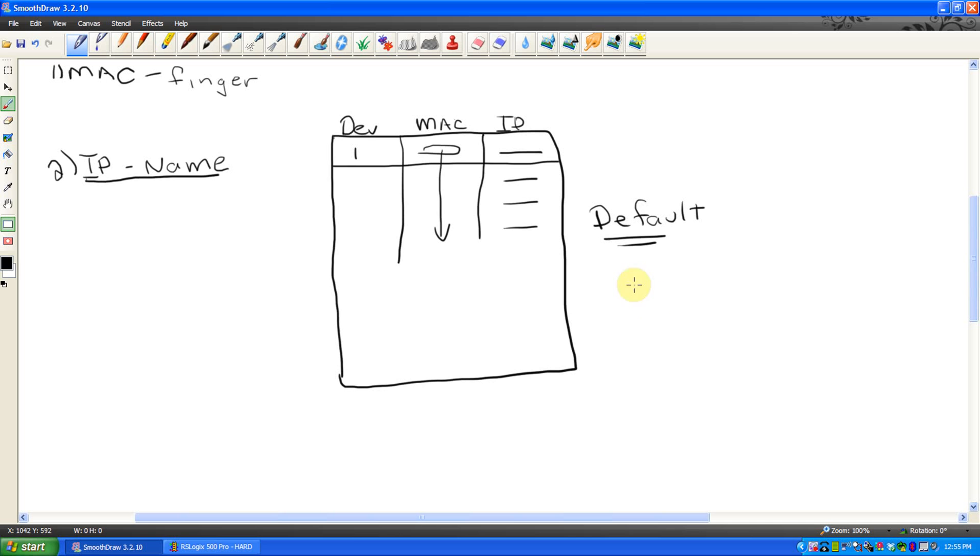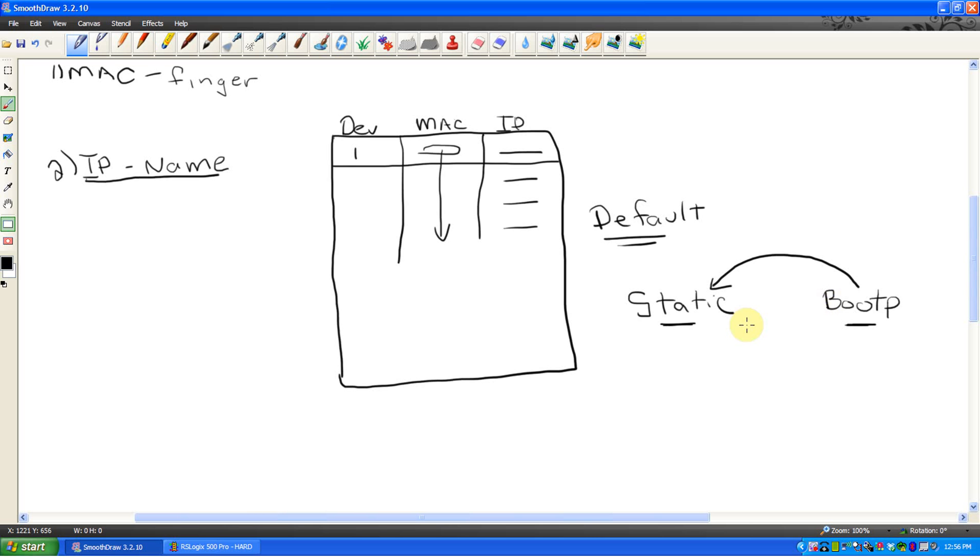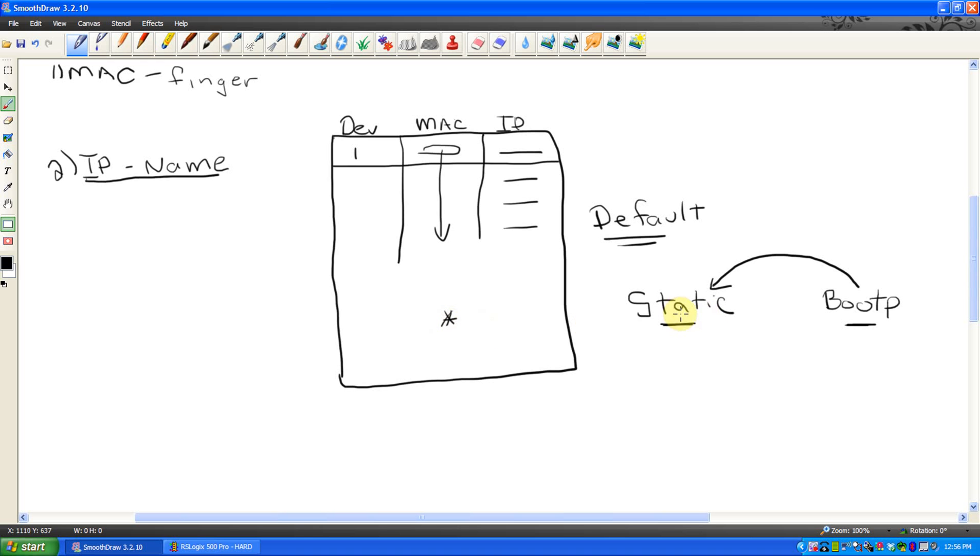That's why when we choose to run static in our lab which we need to run, and the PLC is currently, or when you create a new program, that new program sets up for boot P. The issue is that this is what we want, this is what our software currently when we create a new program has. So the problem is when we try and take this program now dump it into our PLC, the PLC goes wait a minute I'm currently static and you're trying to change me to boot P? Do you want to do this? And of course we're saying don't apply. Our options would either be set this boot P server up in our lab. The problem is every PLC in our lab has the same IP address. That becomes an issue because obviously then there would be conflicts. Two, our lab is not networked properly and three, Windows 7 doesn't really support this all that well yet. At least our image doesn't. So we're going to stay with static.